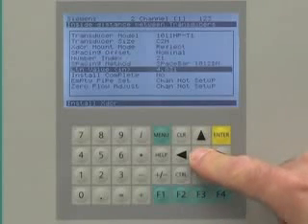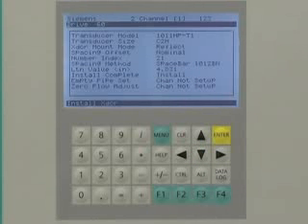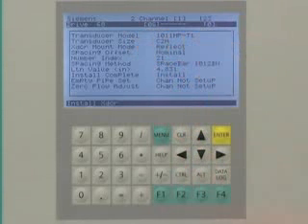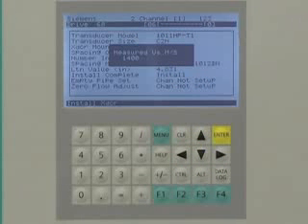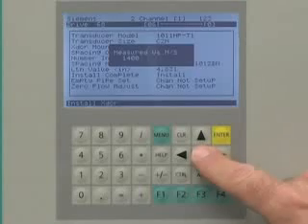We are now ready for the final step in the commissioning of the Sitrans FUS1010. Return to the install sensor screen. Navigate to the install complete menu selection and select install. During this procedure, the FUS-1010 will display a series of drive numbers while it optimizes the sensor frequency. Once the frequency has been selected, a bar graph will be displayed as the operating parameters are verified. Upon completion, the FUS-1010 will display the measured sonic velocity for your liquid. Press the down arrow to continue.